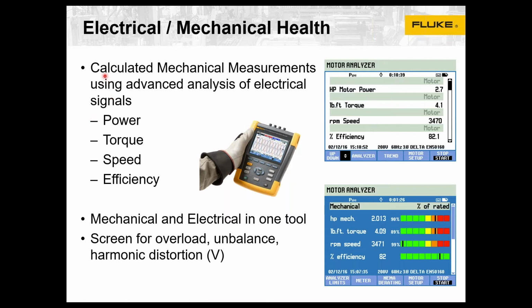Some of the power analyzers on the market now, here's an example of one that can not only measure electrical power, but through the electrical connection can derive speed and torque, which lets you calculate mechanical horsepower and then mechanical efficiency. There's a lot of things on the mechanical side, or how you're operating those motors, that can shorten the life of the motor. Heat's one of the main enemies.